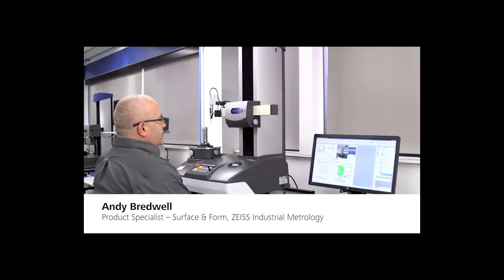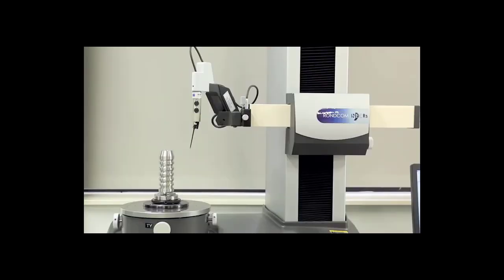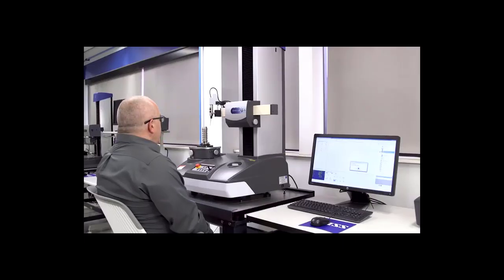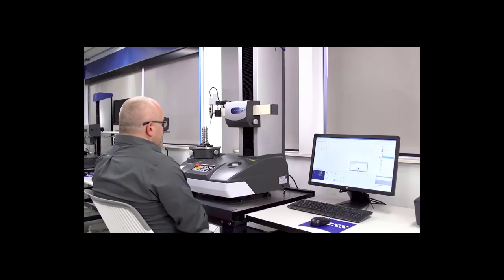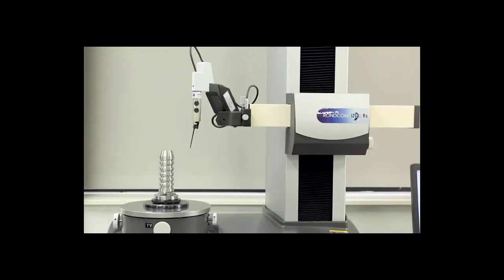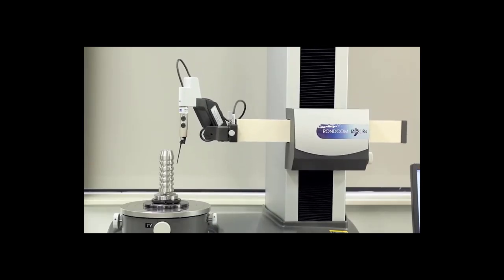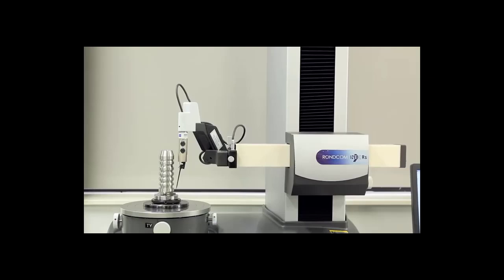Hello, today we're demonstrating the Rondcom RS300 and some of the CNC capabilities. This machine has the mp4 software which will be running and managing this machine. From here we move into a part alignment. The Rondcom 100 is a manual alignment, but the Rondcom 200 and 300 series have automatic programmable alignment for centering and tilting with a wide range.